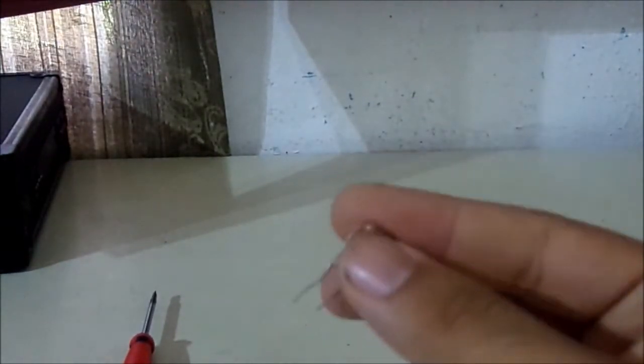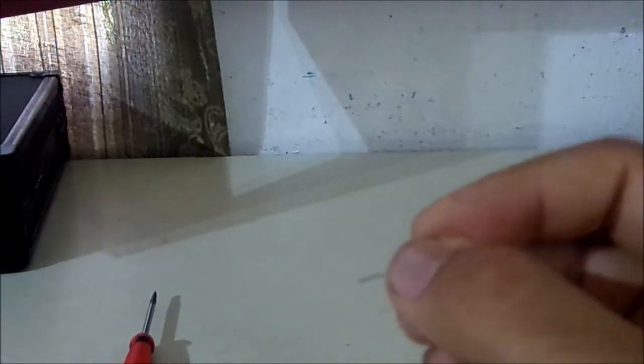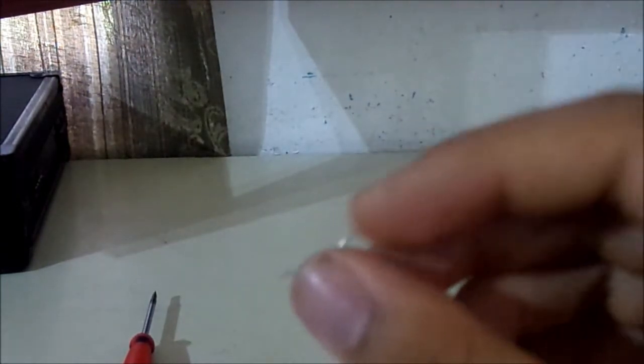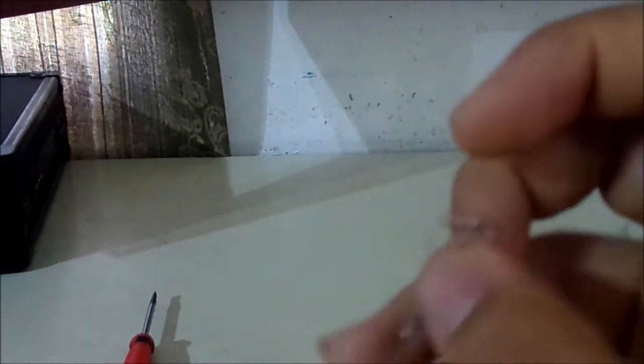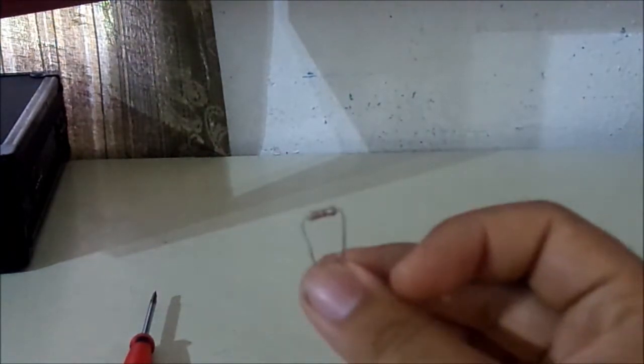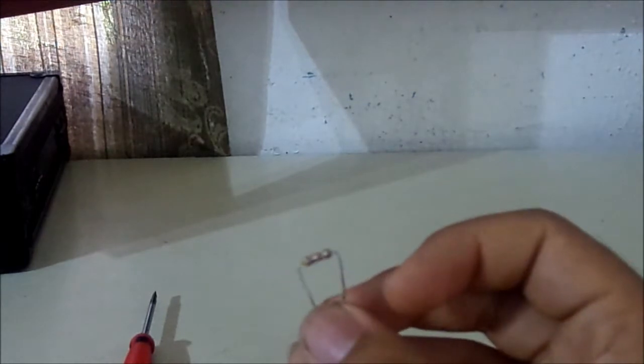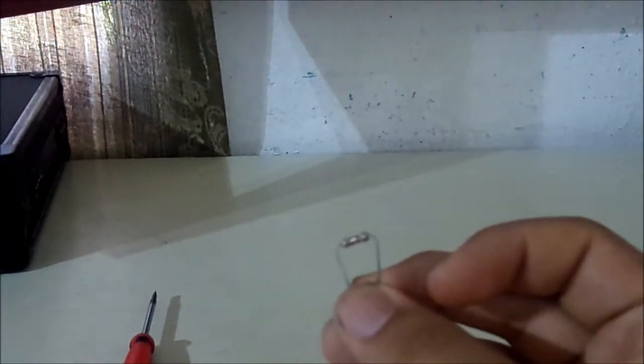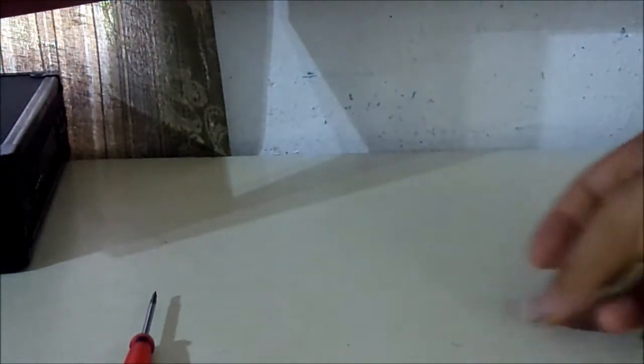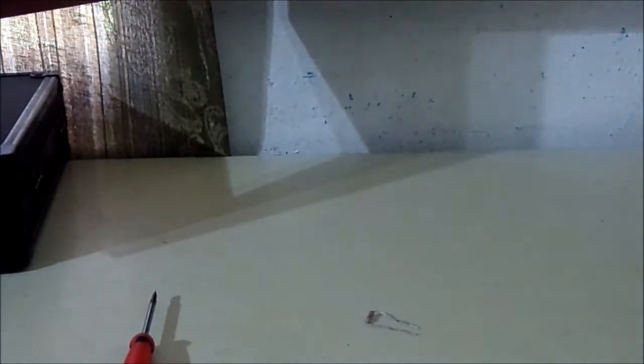So basically, this resistor is used at the end of each device lines of circuit. What this does is tells the control panel that this line is complete. And if it just goes missing, your fire alarm control panel will go to trouble. This is basically helpful to indicate any broken line in the circuit. So you need like six of these.